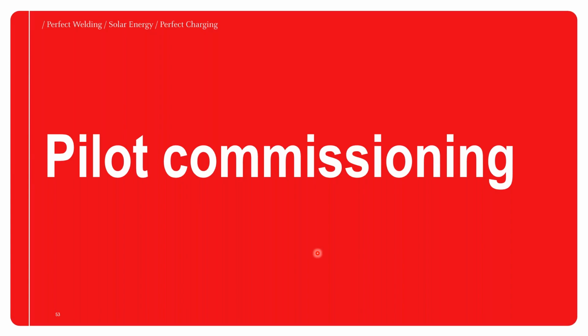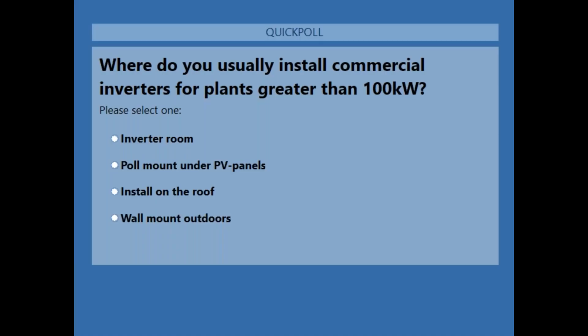Okay, I will now do one poll before I hand over to my colleague Cyprian. I really appreciate if everyone could share their input to this poll. The question is, where do you usually install commercial inverters for plants greater than 100 kilowatts? Do you install it in an inverter room? Okay. Do you pole mount it under PV panels? Do you install it on the roof? Or do you wall mount it outdoors? I'd really appreciate your response. And I will close the line in about 10 or 15 seconds.